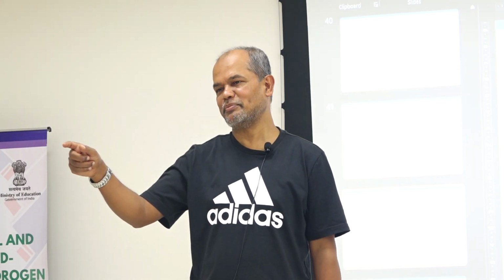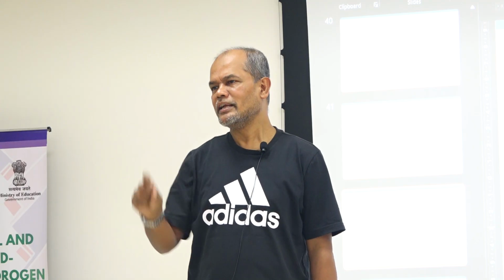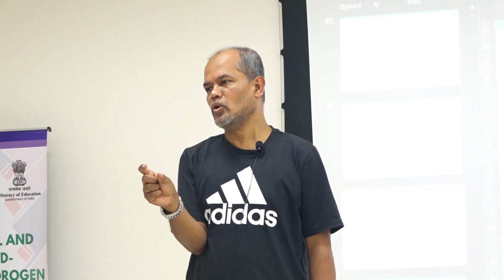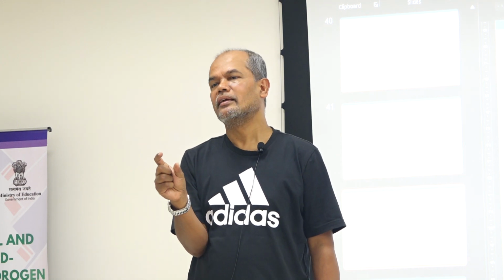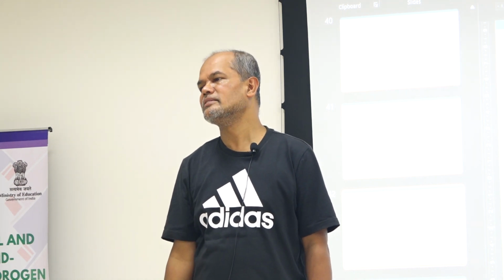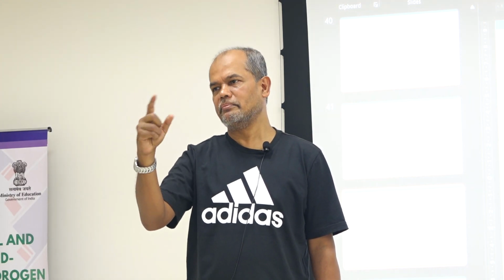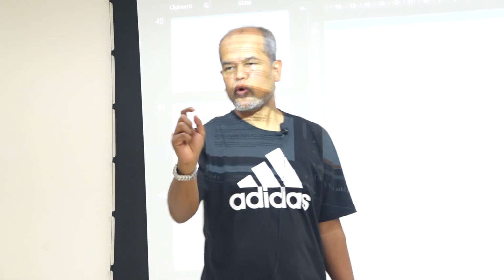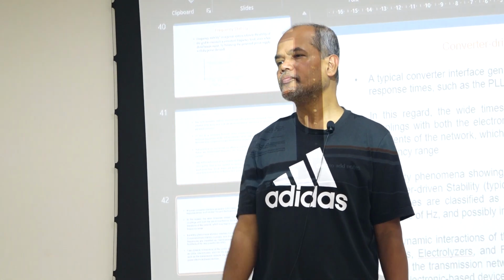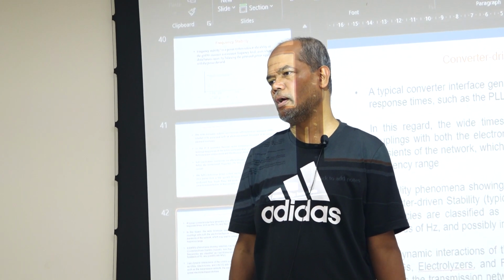But the thing that I was explaining, that when you have more inductive load, induction machine load in the system, that might cause the instability problem. Because what happens when a motor starts, to energize the magnetic field, it takes more reactive current from the system, right? And when it takes more reactive current, that actually causes voltage drop in the system, and that introduces voltage instability.